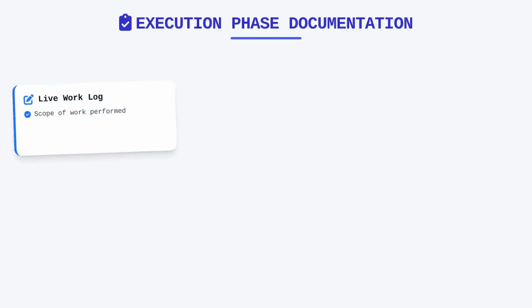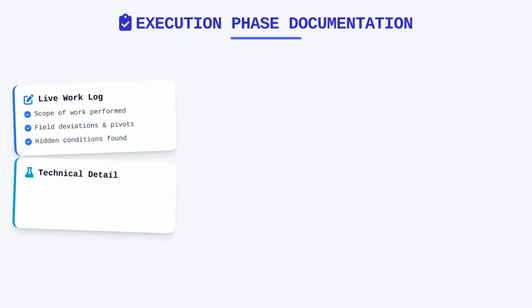During the execution phase, you need to maintain a live log that reflects the scope of work performed and any necessary field deviations. It is common to encounter hidden conditions that might require a pivot from the original project plan, and these moments must be documented with precision. You should record the specific mechanical methods employed, the cleaning agents used, and any challenges that influence the final outcome.